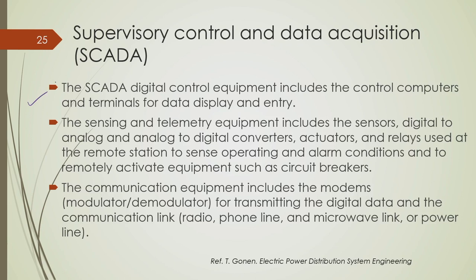SCADA includes digital control equipment, sensors and telemetry equipment, two-way communication as its backbone, a master station, and many remotely controlled stations. The digital control equipment includes computers and terminals for data display and data entry. Sensing and telemetry equipment includes sensors deployed in different parts of the network, digital-to-analog or analog-to-digital converters, actuators, relays, and equipment to operate circuit breakers remotely.